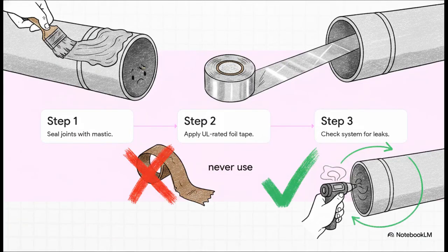To stop that energy loss dead in its tracks, we follow this exact multi-step installation protocol. Step 1. We physically paint and seal every single joint and connection with a heavy-duty mastic paste. Step 2, we apply UL-rated foil tape right over that. And let me be super clear about this. We never, ever use standard cloth-back duct tape. That stuff just dries out and peels right off in attic heat. Finally, step 3. We conduct a rigorous, comprehensive check of the system for any remaining leakage. We don't consider the job done until that system is completely airtight.